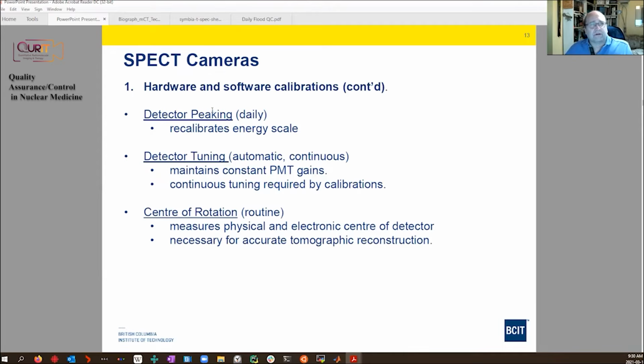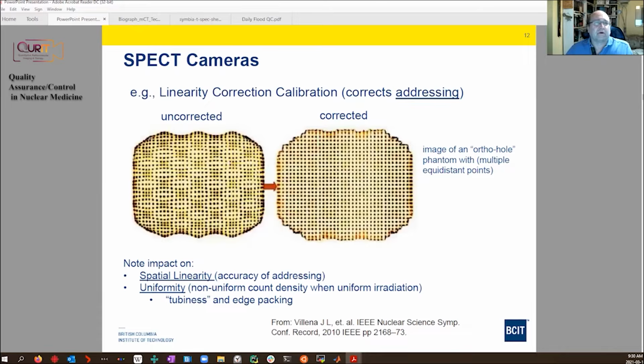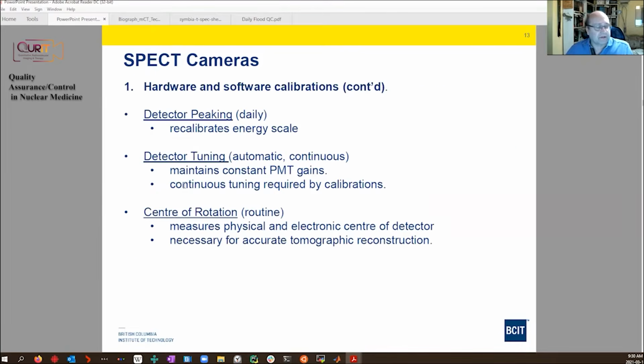Other calibrations include peaking of the camera, which is a procedure that the technologist does, which means the energy window is centered around the appropriate photopeaks in the energy spectrum. This recalibrates the energy scale. The detector also requires tuning, that is, if you want to ensure that all the PMTs have the same gain. If one PMT begins to have more gain than the others, it will actually affect the uniformity. And so there are systems that continuously tune the camera.